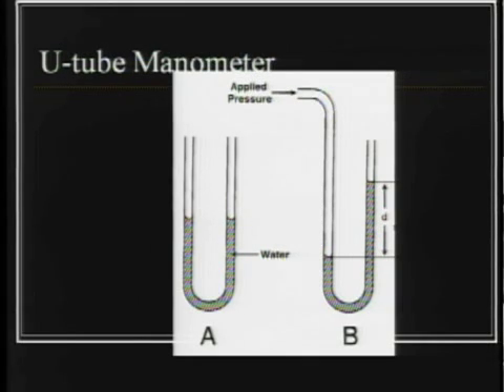And we'll see a picture of this in a video in just a little bit that will clarify it even more. But you're really talking about how much force it takes to displace a column of water. And that's why it's measured in centimeters of water. So I could put my lips at the end of the tube on that U-tube manometer and go, and I would see how much force, how much fluid was displaced when I built up the pressure for that P. And you would measure that, and you would say, okay, I had 3 centimeters of water pressure built up for the P production. Okay, so when you're thinking about the gold standard or what to calibrate with for a pressure transducer, you calibrate with a manometer.